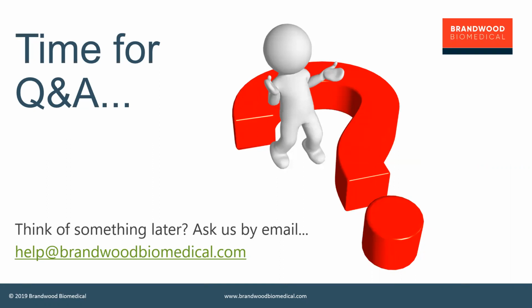So testing something that's manufactured from the final materials, manufactured using the same processes. And I suppose if you do introduce a late change in the manufacturing process or whatever, then you may need to do a bit of supplementary chemistry, but you may be able to justify the change. That's right. And there is a lot of evaluation that goes on here. You need to put the options side by side and say, are these the same? And if they're not exactly the same, how much does it matter? So evaluation is pretty important here.